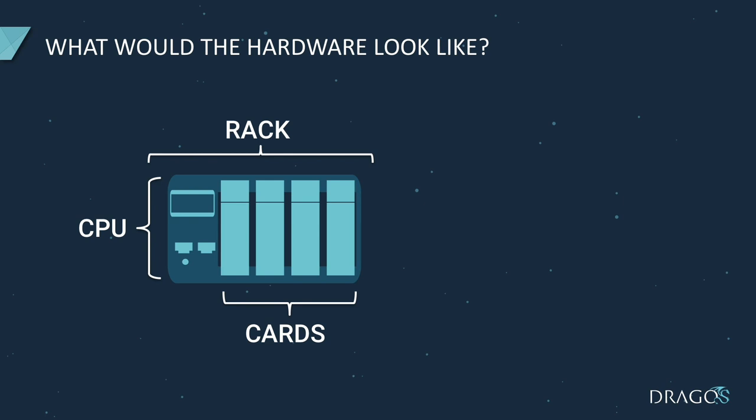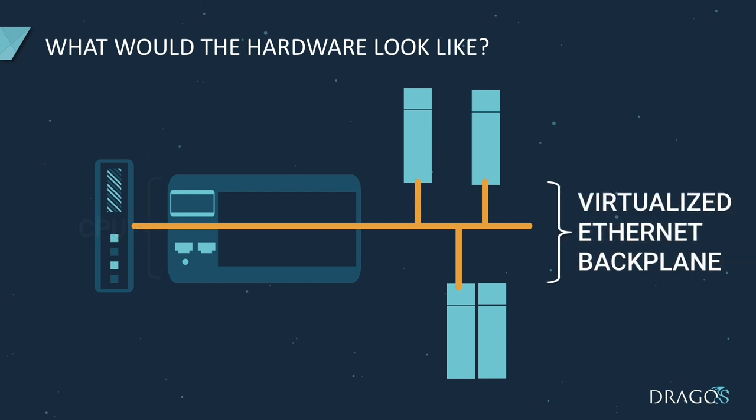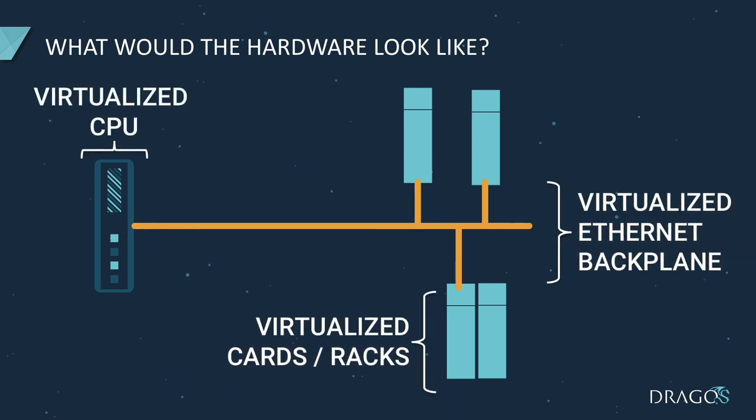If we were to create a virtualization layer around this, suddenly we're able to potentially get rid of the rack, replace the CPU with maybe an industrial PC or a proper server depending on environmental conditions. We're able to move racks and cards around — because the whole backplane is virtualized, those cards could be anywhere and the PLC would still believe they're on the same physical rack. Moving that backplane to a low-latency fiber optic network rather than the old serial bus would allow it to spread across a plant and allow much more flexibility in how those cards are deployed.